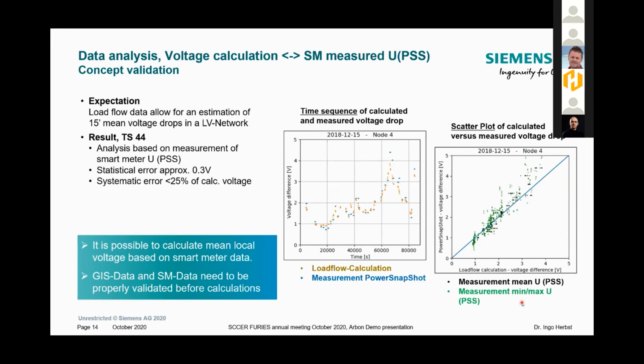In fact, because this calculation takes the mean of 15 minutes, we compare here the mean, which we can trigger, against a min or max during this 15 minute trigger time. The min max is of course a bit higher, and the black one follows nicer to the mean value calculated from load data.